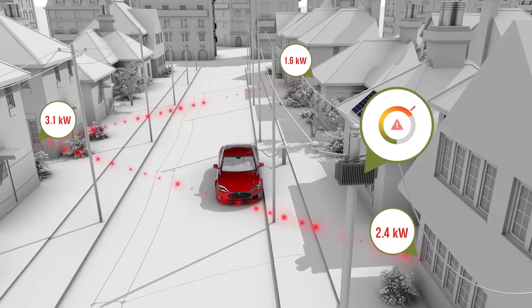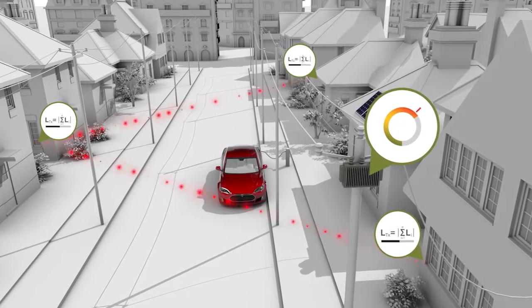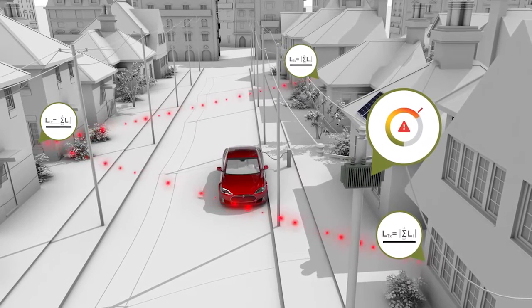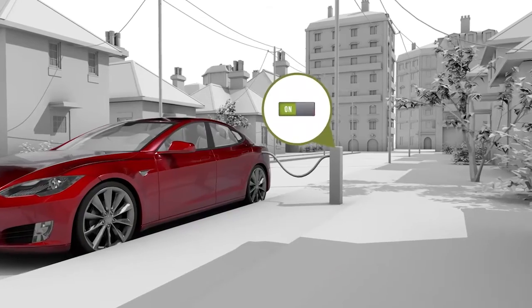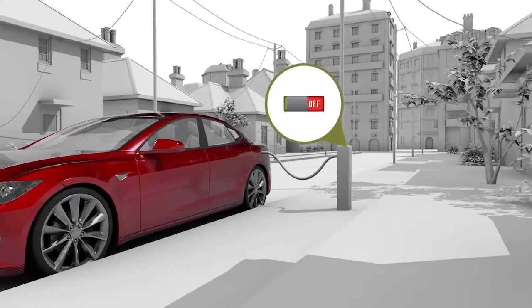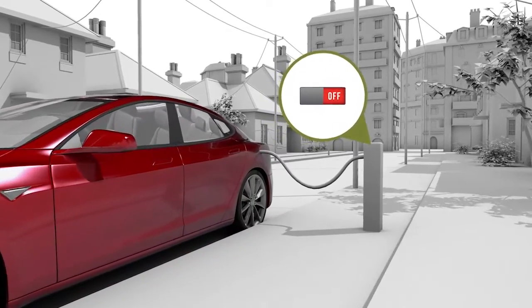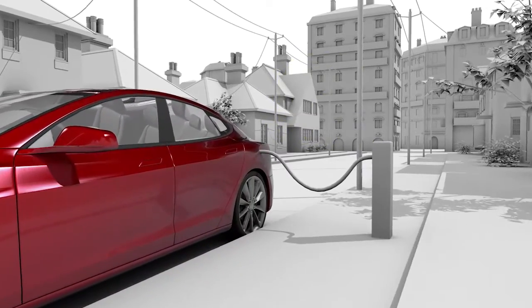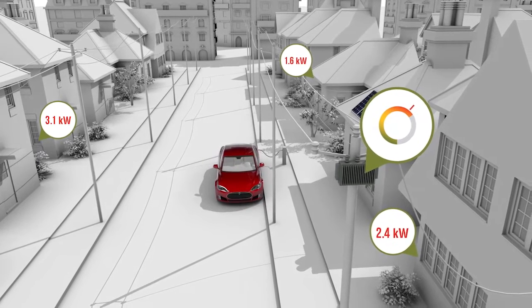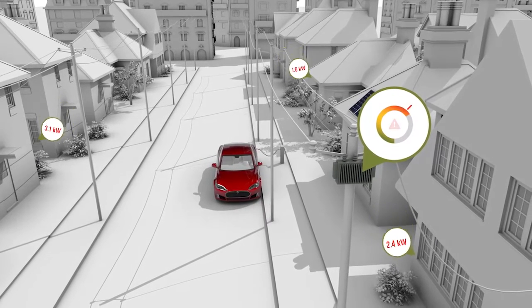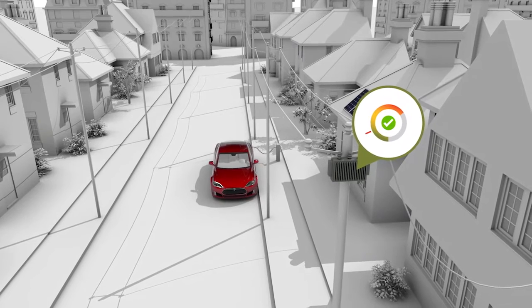When this occurs, a distributed analytic running on the OpenWay Riva meter determines whether to shut off controlled loads behind the transformer, increase local distributed generation behind the transformer, or take other action to protect the transformer against overload and failure.